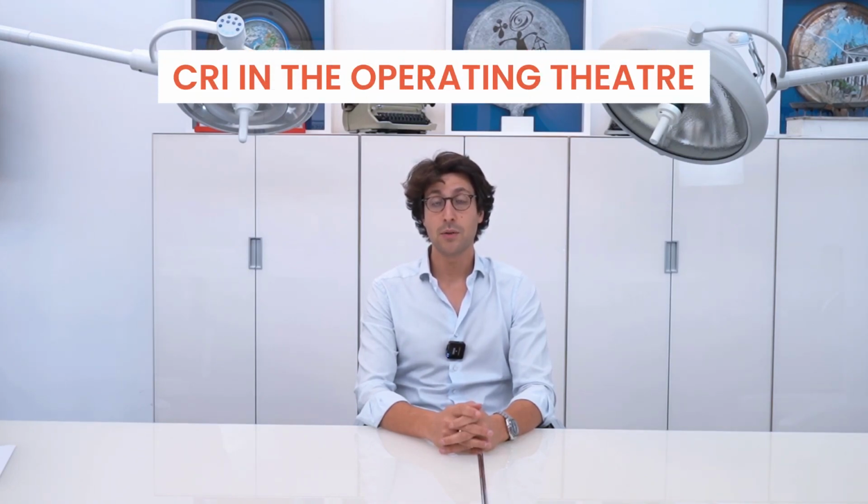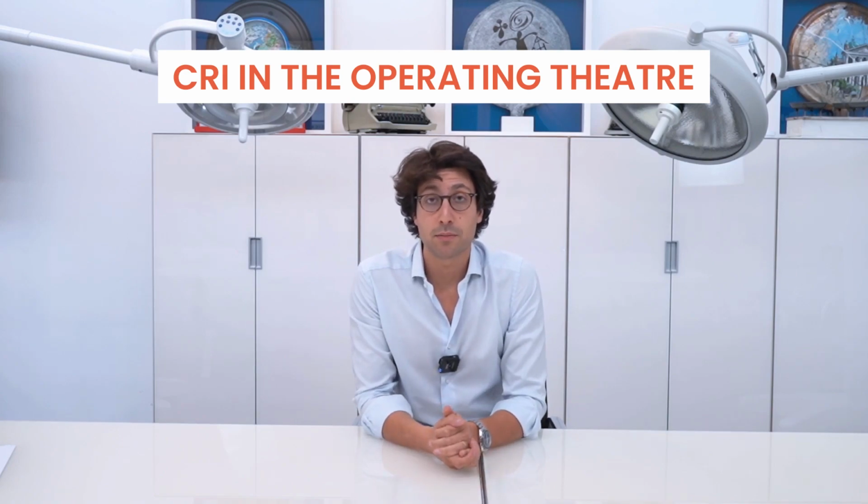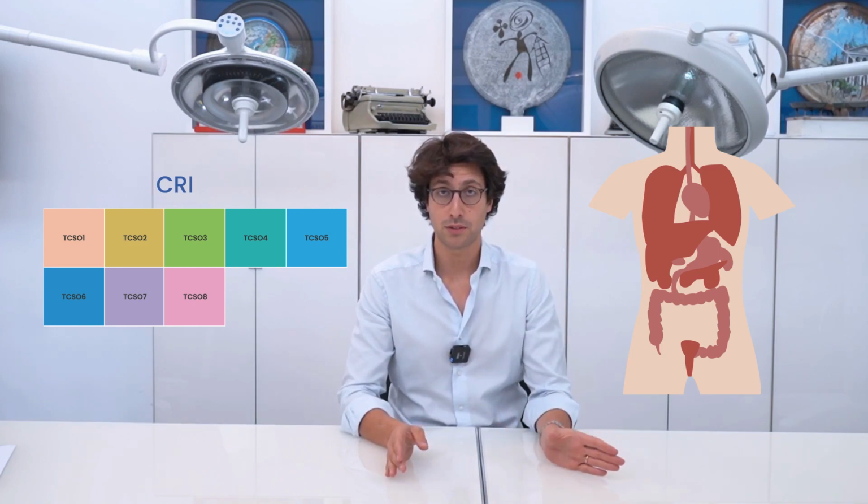Several criticisms have also been submitted with reference to the color rendering index used in the operating field. The first criticism made by the researchers is about the test colors. The 8 test colors are not really representative for the medical environment, since these 8 samples lack the analysis of red, called R9, i.e. the 9th test color, which is really needed in the analysis of a light for operative purposes. What happens then in the surgical environment is to consider the color rendering index and integrate this value with the color rendering for R9, since red is a fundamental color during surgeries.